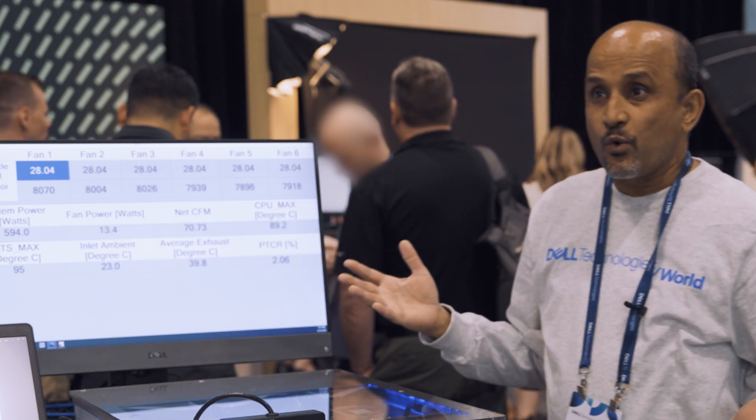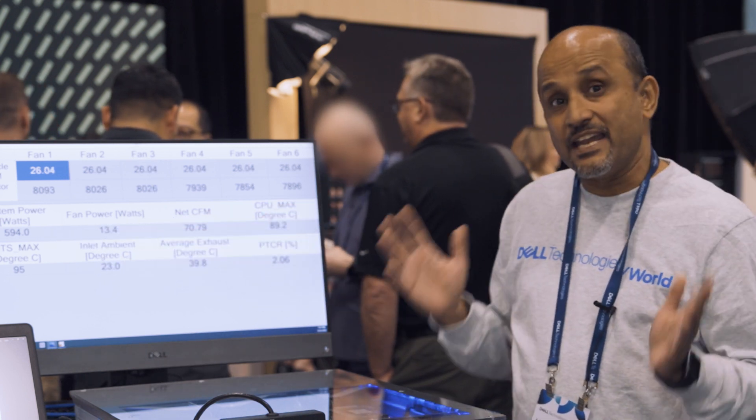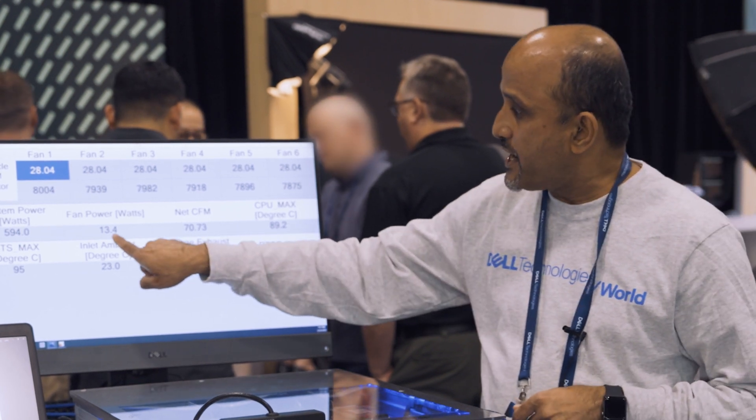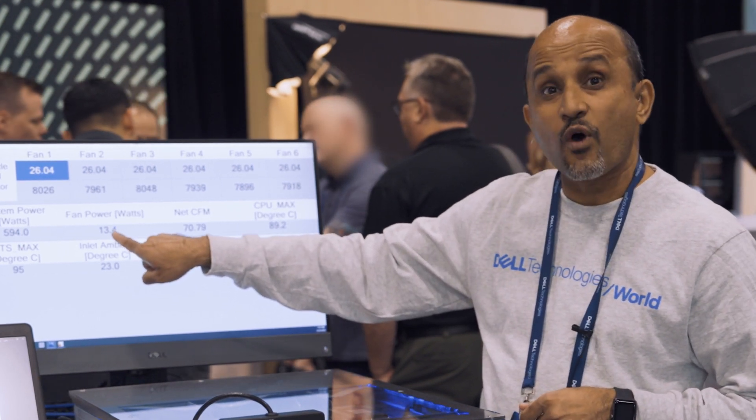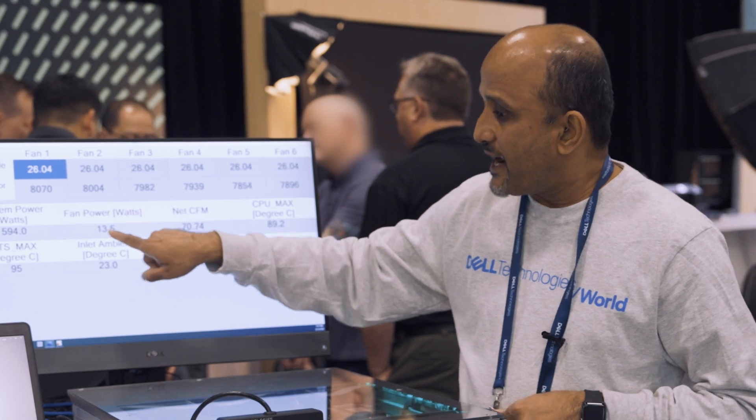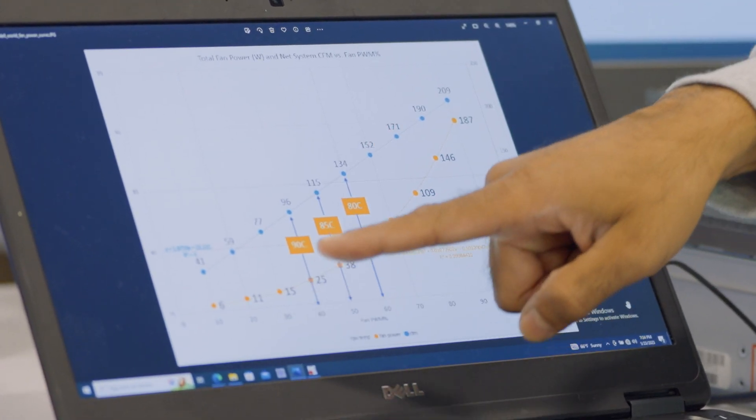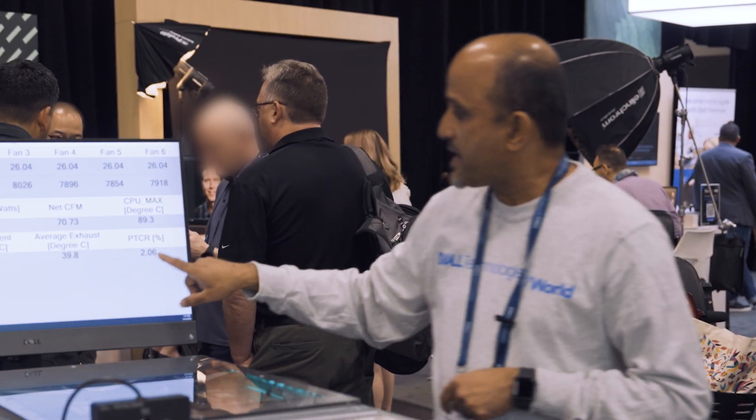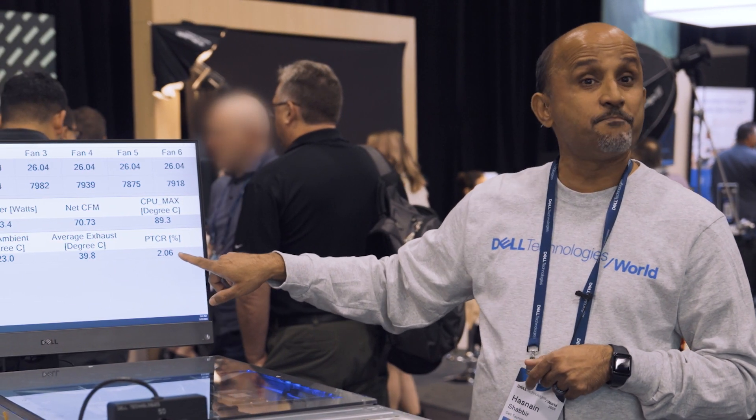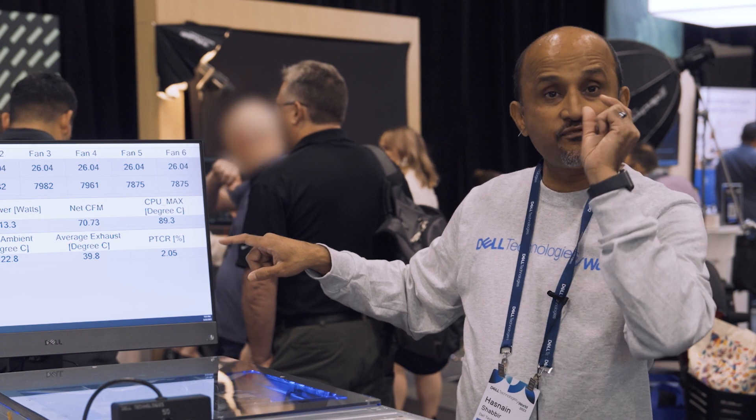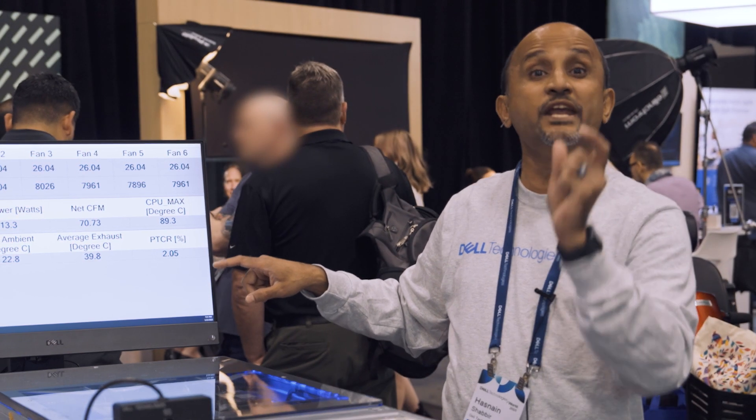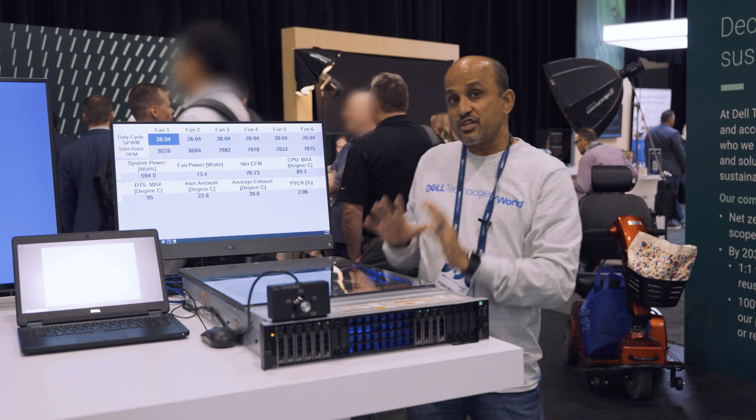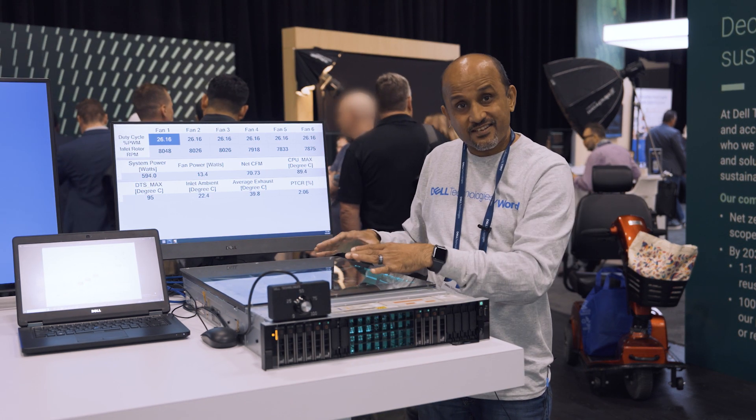I'm not over cooling, I'm not wasting any power. By doing that, I'm only consuming 13-14 watts of fan power right now. That's only about two percent of the system power, a very small chunk of system power being consumed for cooling. If somebody doesn't do a good job of controls on this box and over cools things, you will start moving on this curve.